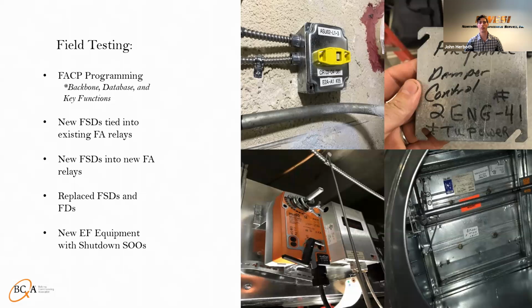And it all comes down to the identification and how it's been named and naming conventions in the programming for a fire alarm contractor to do that. So you'll have much better luck with a new project, obviously, because everything is fresh. But on an existing hospital that's had so many remodels, you end up having some problems just from the method of testing. So that is one issue that you're going to have to tackle on each individual project.